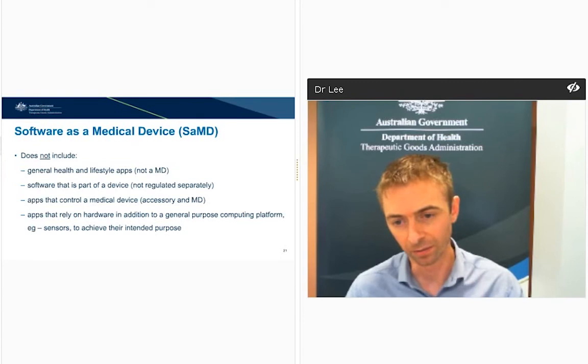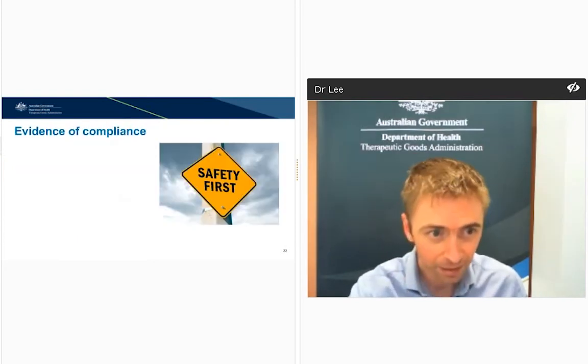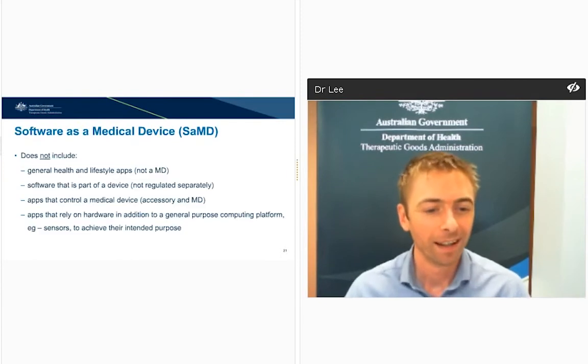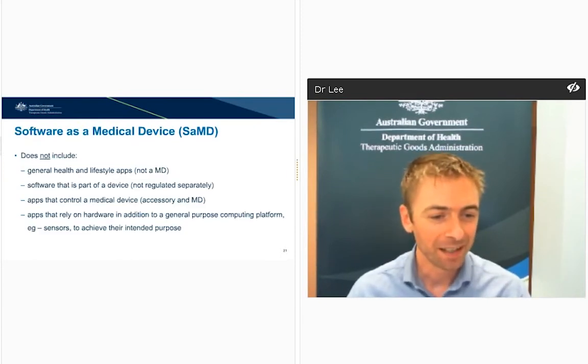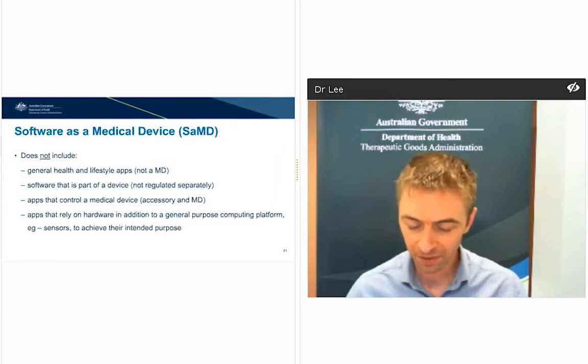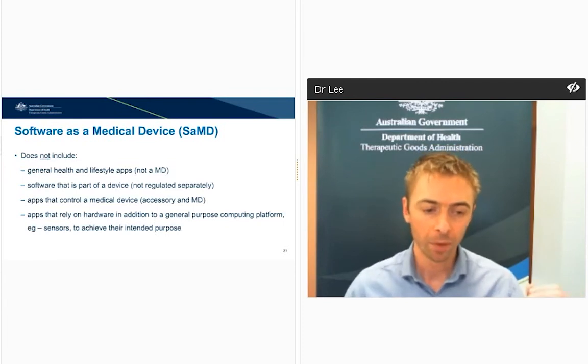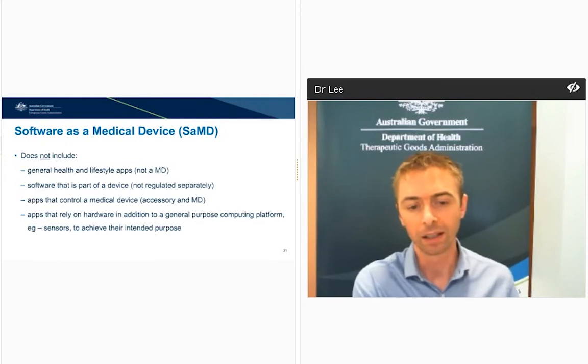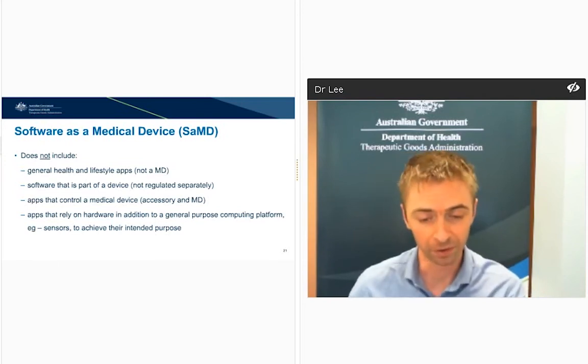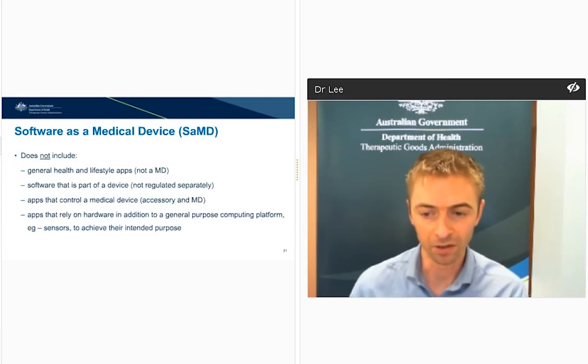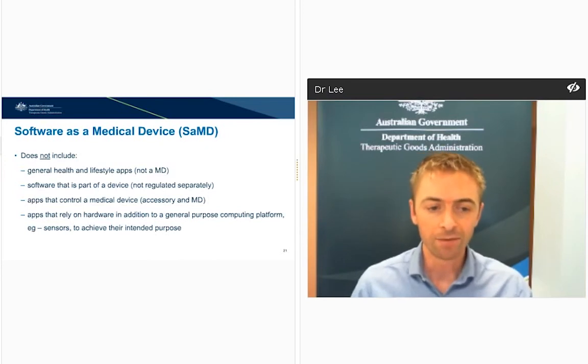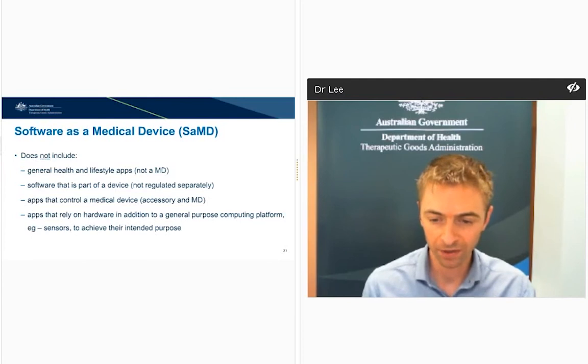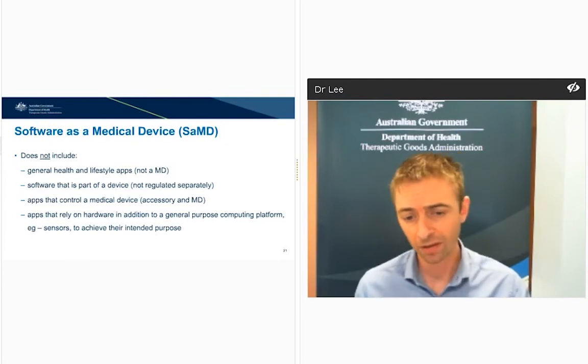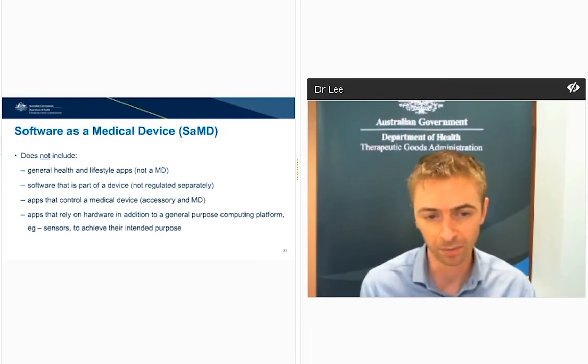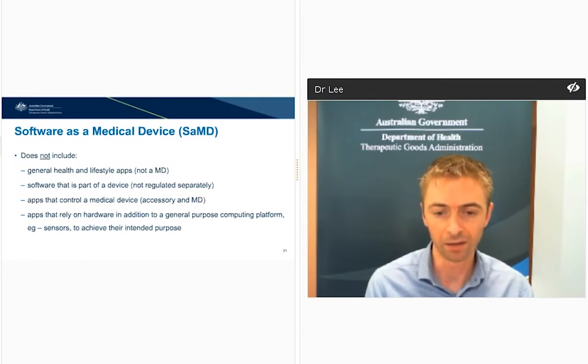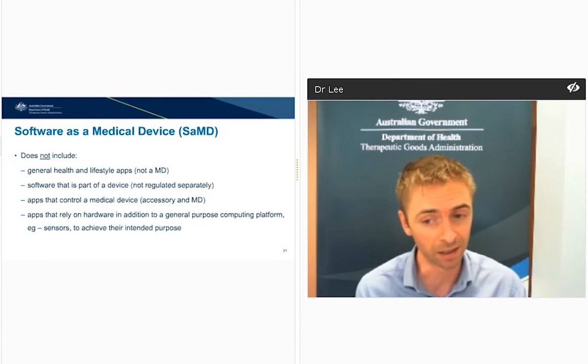An example would be the image processing software I talked about in the previous slide, where the image might be captured somewhere else, say on an X-ray machine or an MRI, and then uploaded to a server and the radiologist does something with it. That software is not capturing the image, it's receiving the image and doing the processing. If you've got an app on your phone that's taking a picture of something and then making a decision, it's dependent on the camera as a sensor, and therefore the sensor becomes part of the system and part of the medical device, and they're regulated as such.